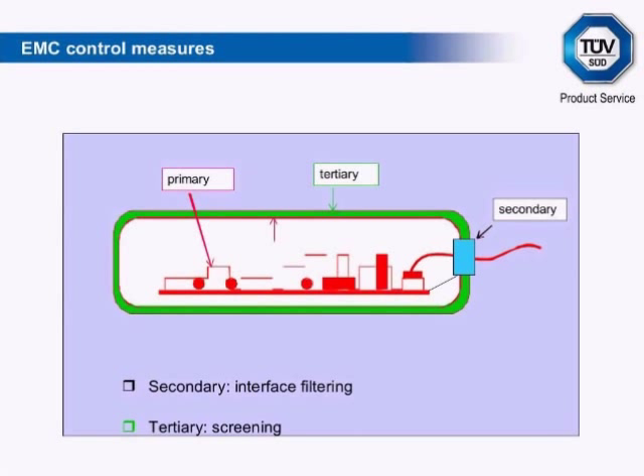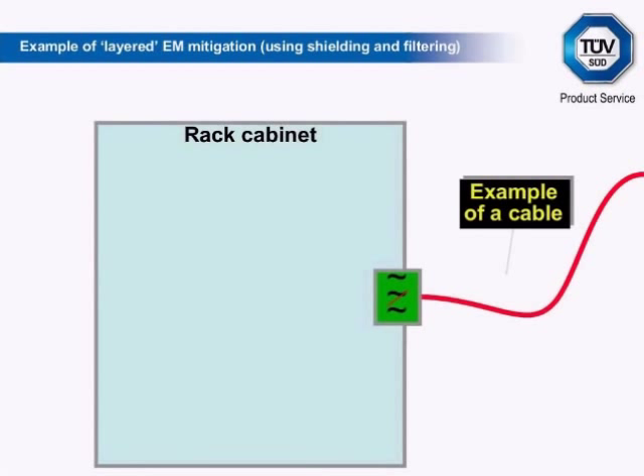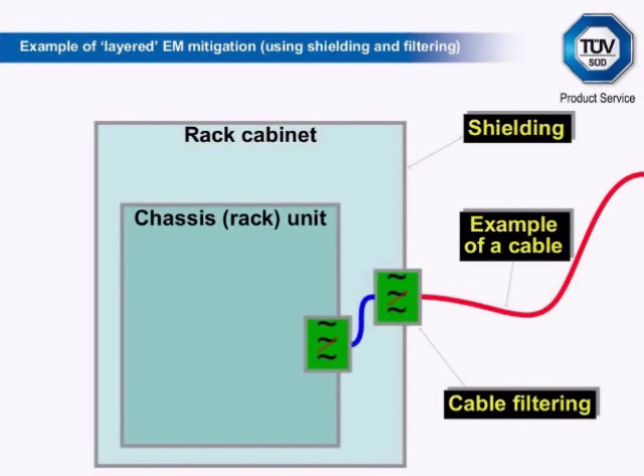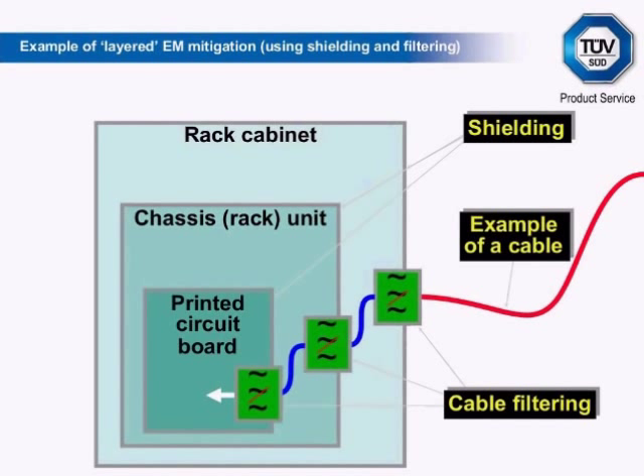Choice and mounting of connectors forms an important part of secondary-level EMC control. Full shielding at the tertiary level is an expensive choice and should only be chosen when all other measures have been applied. But since it is difficult to predict the effectiveness of primary measures in advance, it is wise to allow for the possibility of being forced to shield the enclosure. At the system or installation level, further measures include cable routing and segregation, as well as system-wide grounding and bonding. In a layered EMC mitigation example using shielding and filtering: a cable enters an equipment rack enclosure with filtering on the cable and shielding provided by the rack cabinet. It then passes into the chassis through a second filter, with the chassis itself providing additional shielding. Finally, the circuit has filtering on the cable again, plus a shielded enclosure around it.